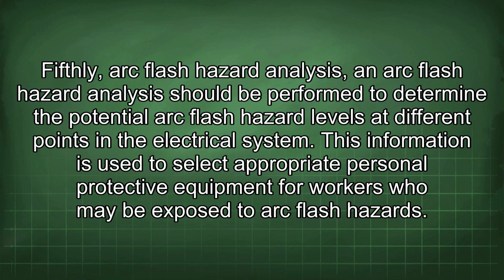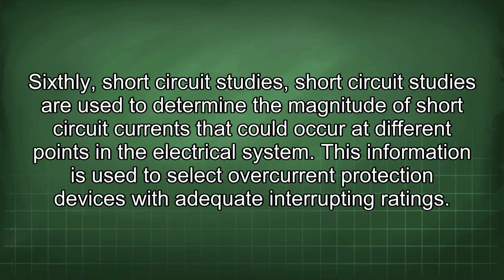Fifthly, arc flash hazard analysis. An arc flash hazard analysis should be performed to determine the potential arc flash hazard levels at different points in the electrical system. This information is used to select appropriate personal protective equipment for workers who may be exposed to arc flash hazards. Sixthly, short circuit studies. Short circuit studies are used to determine the magnitude of short circuit currents that could occur at different points in the electrical system. This information is used to select overcurrent protection devices with adequate interrupting ratings.